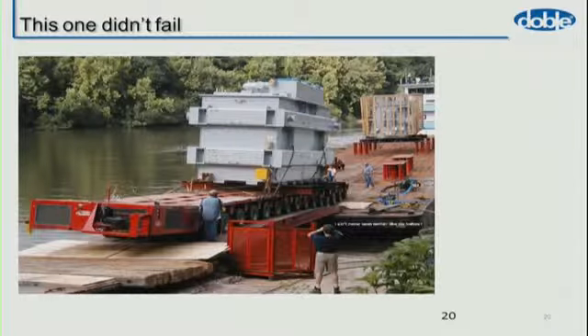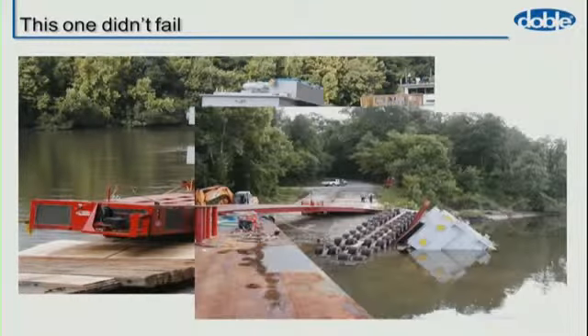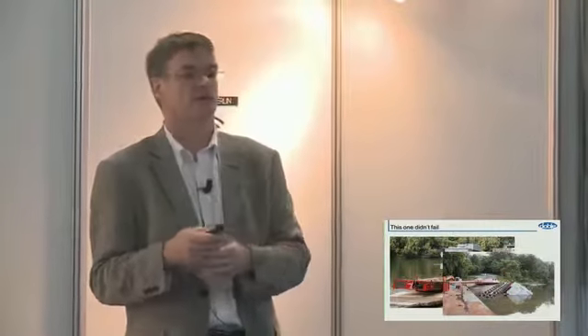This transformer hasn't failed. It's the same transformer. It still has not failed. It was pushed. It didn't fail. Something else damaged it. So you have to be very careful about failure statistics. And now the consequence is going to be, is there any oil from the transformer in the river? That's going to be a cleanup cost, which the company is liable for. And in the UK, in Europe, not the transportation company, the owners of the transformer are liable.